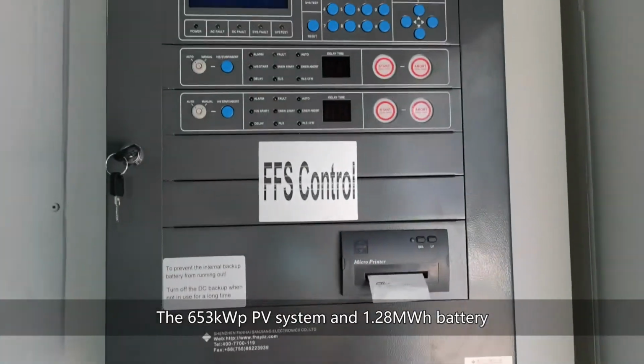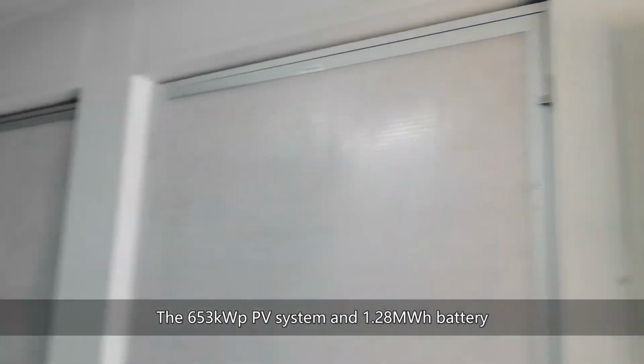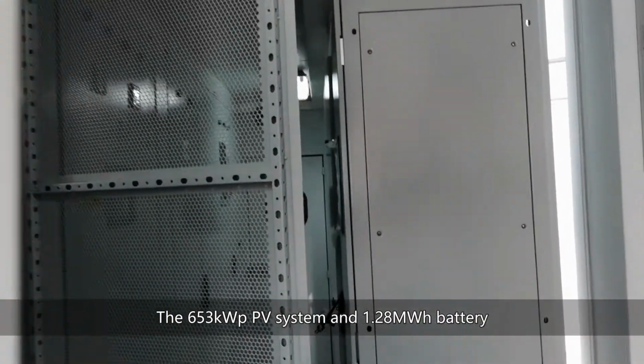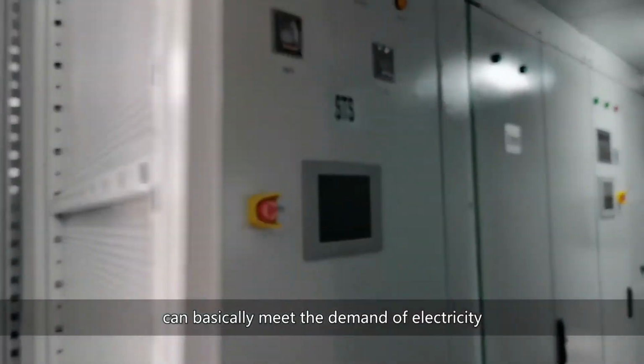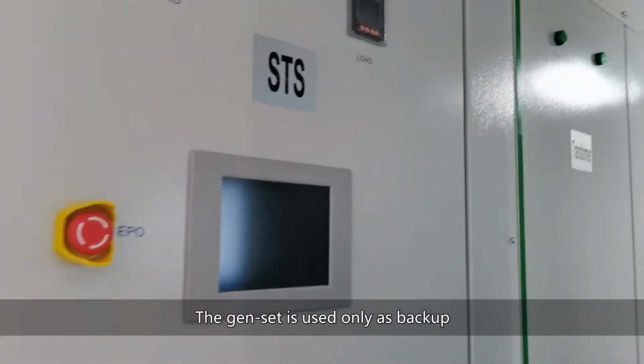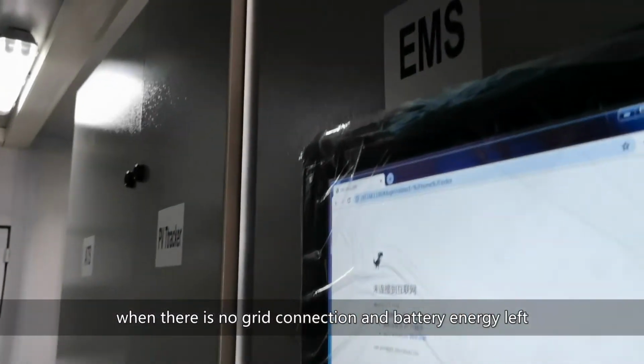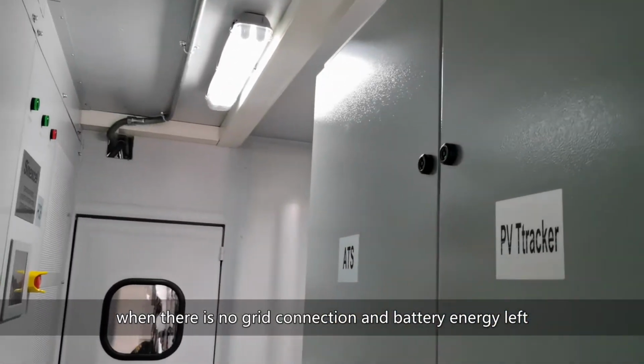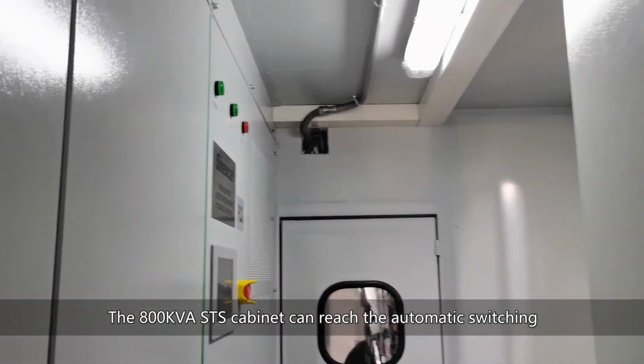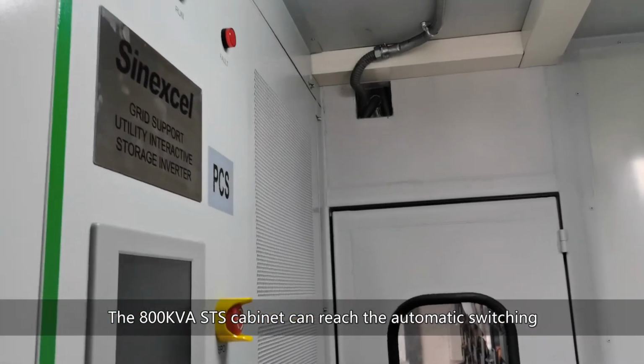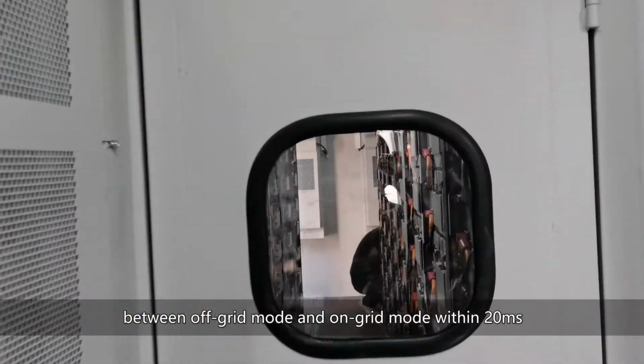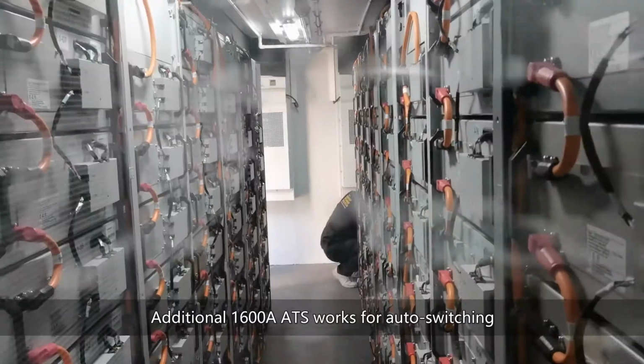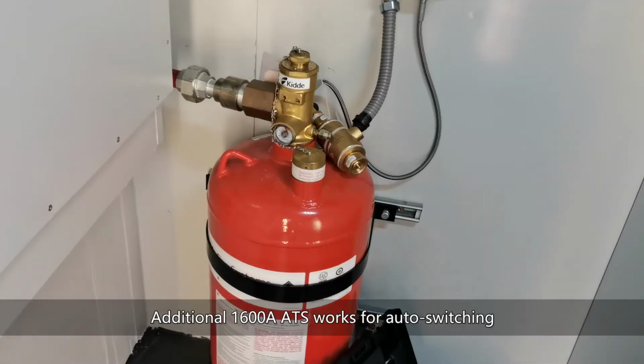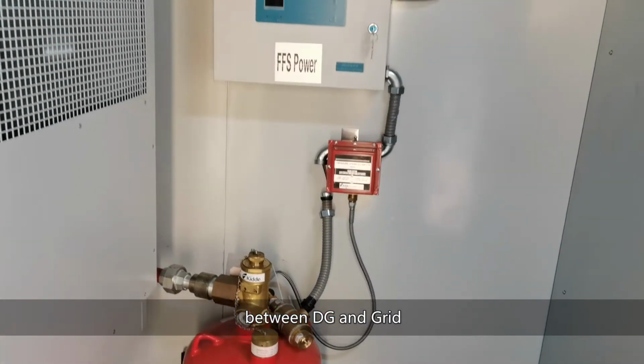The 653 peak kilowatt PV system and 1.28 megawatt-hour battery can basically meet the demand for electricity. The genset is used only as backup, when there is no grid connection and no battery energy left. The 800 kVA STS cabinet can reach automatic switching between off-grid mode and on-grid mode within 20 milliseconds. An additional 1600A ATS works for auto-switching between the diesel generator and the grid.